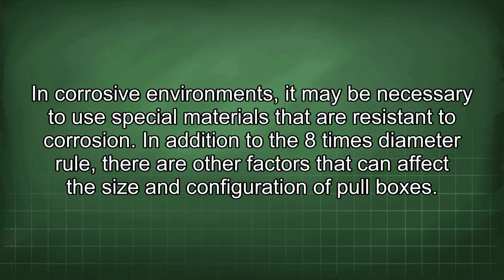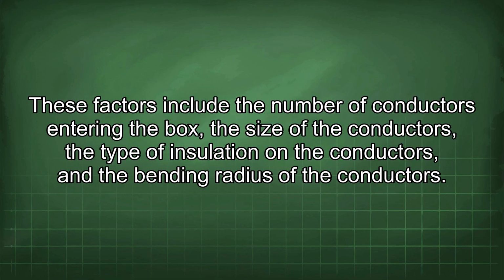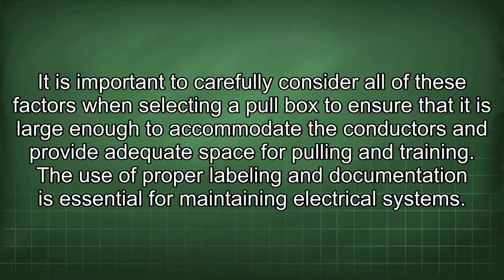In addition to the 8 times diameter rule, there are other factors that can affect the size and configuration of pull boxes. These factors include the number of conductors entering the box, the size of the conductors, the type of insulation on the conductors, and the bending radius of the conductors. It is important to carefully consider all of these factors when selecting a pull box to ensure that it is large enough to accommodate the conductors and provide adequate space for pulling and training.